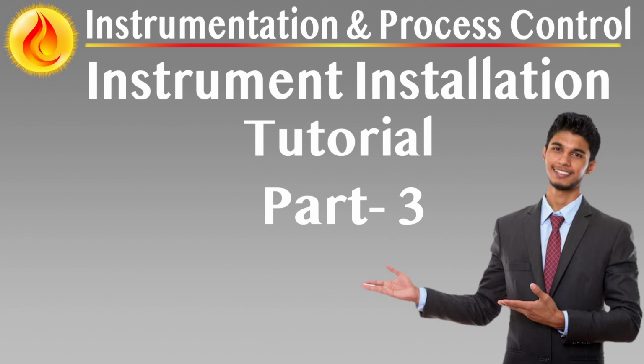Process limitations. Best fit for select services. Self-purging is ideal for low-pressure gas systems, cryogenic services, and clean vapors where small amounts of condensate may form and naturally return to the process. However, it is not suitable for fluids with high pour points, solids, waxes, or reactive components that leave behind residue upon evaporation. In such services, partial evaporation can create scale, coking, or measurement noise, negating the benefit of passive purging. In these cases, active purging or alternative measurement technologies should be considered.